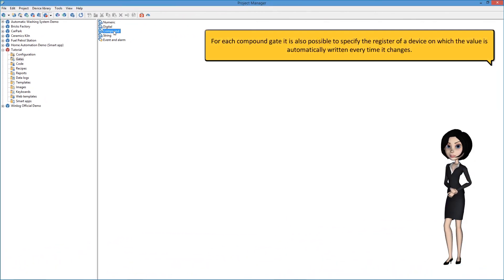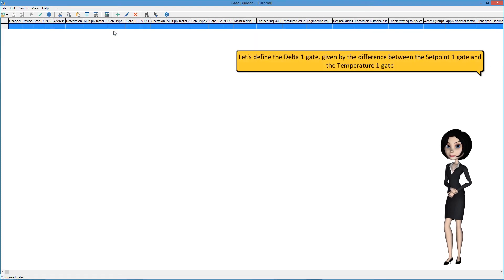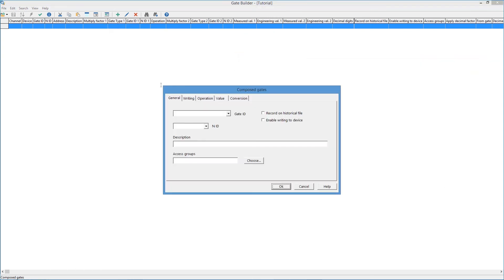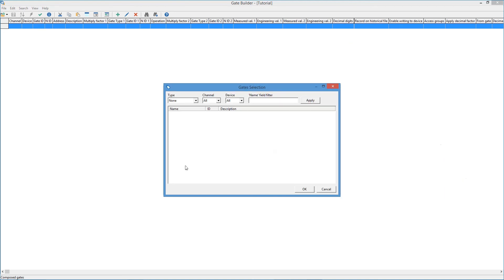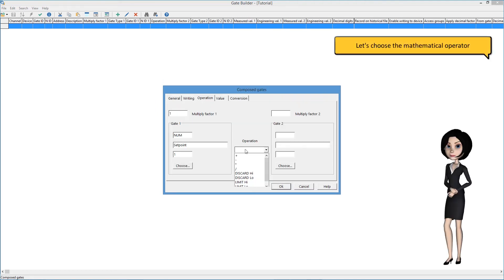For each compound gate, it is also possible to specify the register of a device on which the value is automatically written every time it changes. Let's define the delta 1 gate, given by the difference between the setpoint 1 gate and the temperature 1 gate.